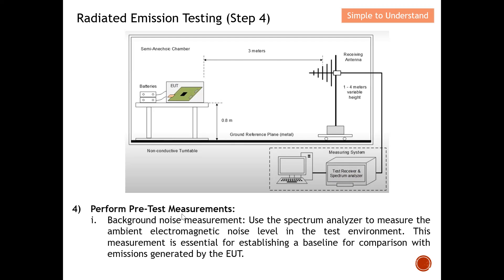Step 4: Perform pre-test background noise measurement. Use the spectrum analyzer to measure the ambient electromagnetic noise level in the test environment. This measurement is essential for establishing a baseline for comparison with emissions generated by the EUT. With the EUT not powered on, do a quick measurement to capture your ambient electromagnetic noise level, so that later you can quantify the radiation from your EUT distinctly.